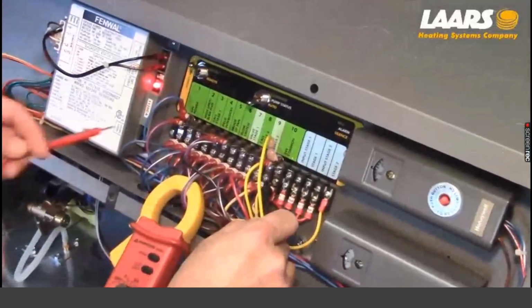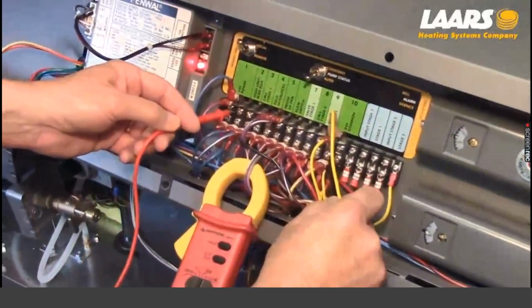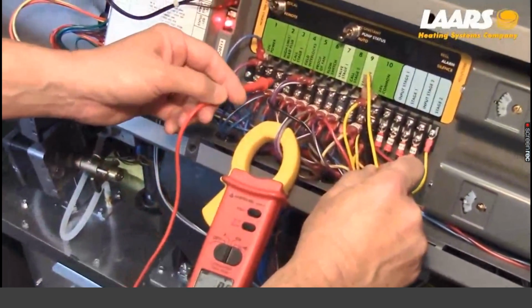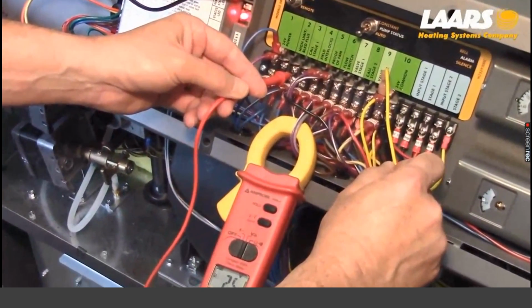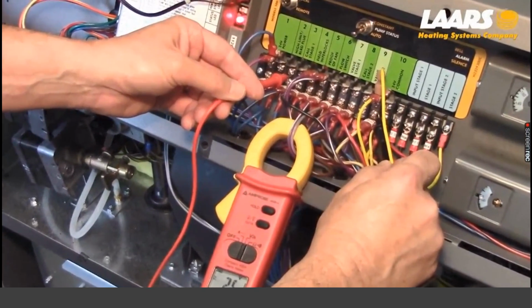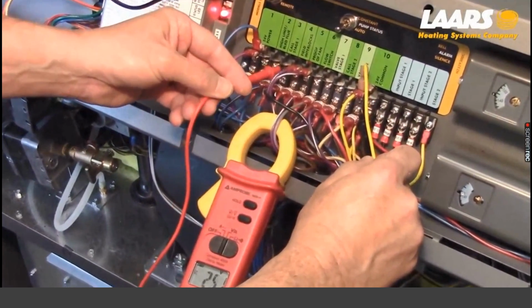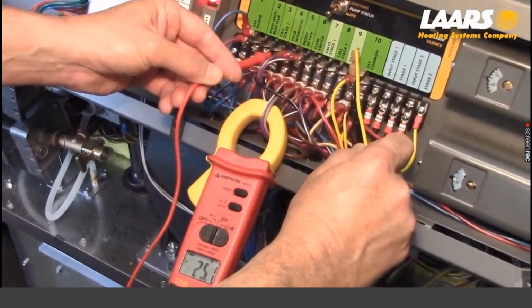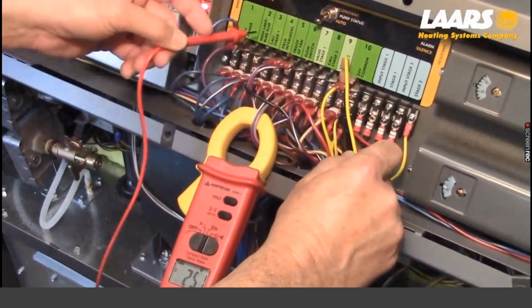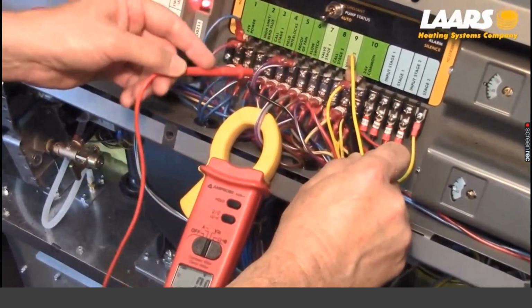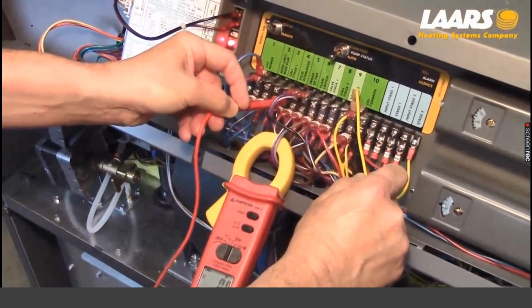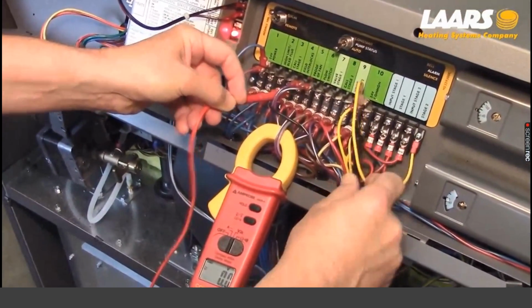So now that you can see I've reset the gas pressure switch, I'll start at terminal 1, I have it, and terminal 2, I now have 25 volts. I'm then going to go to terminal 3. Here's my terminal 3, I have 25 volts there. Terminal 4, which says field interlock, okay, I'm going to go there, and I do not have voltage there.